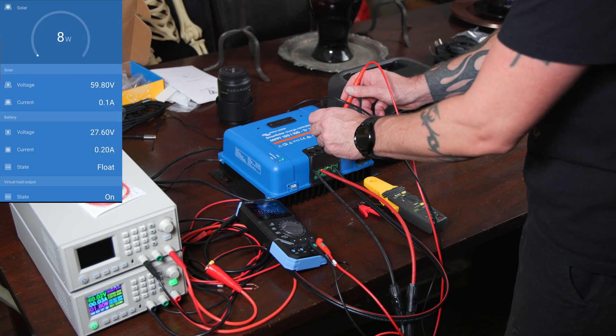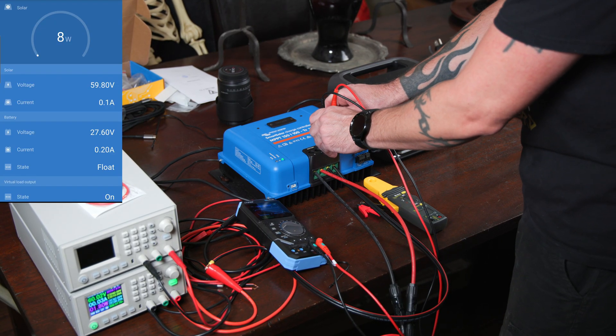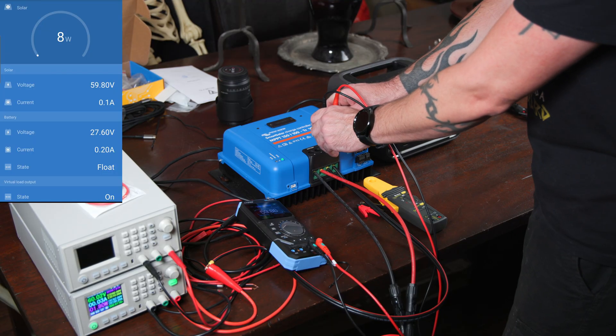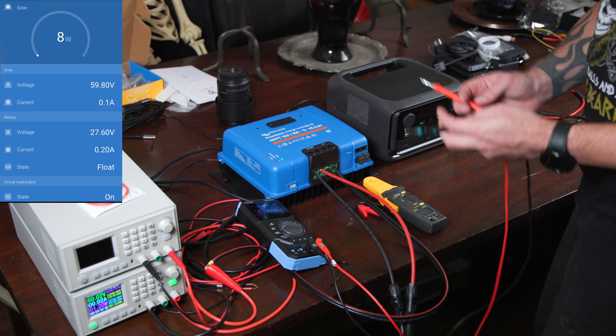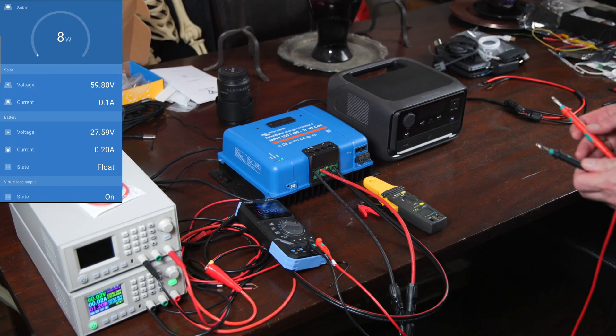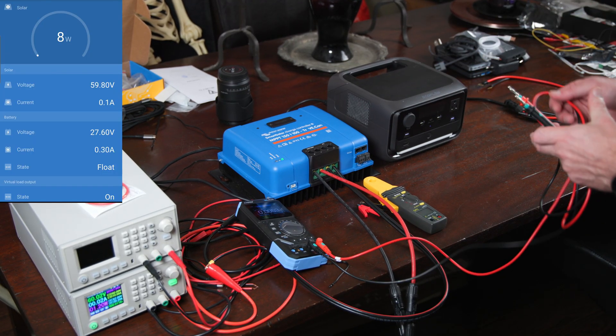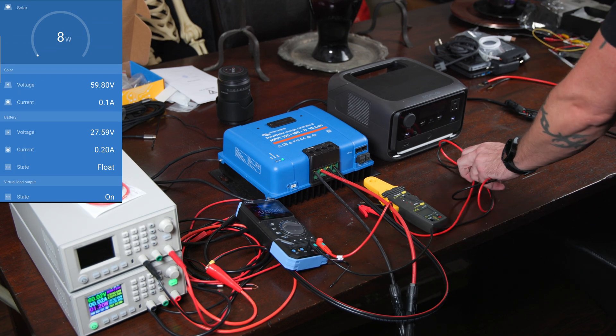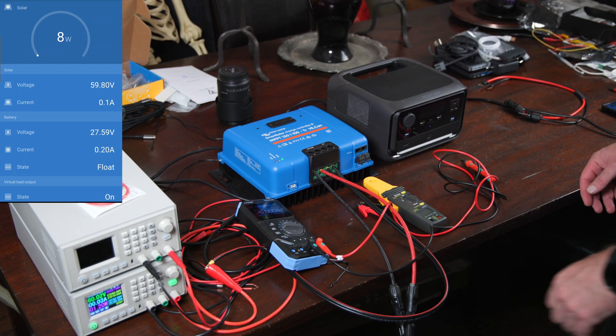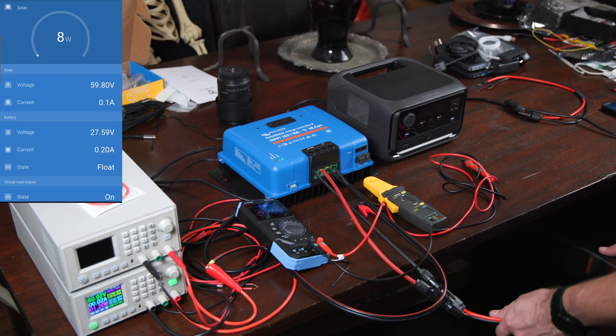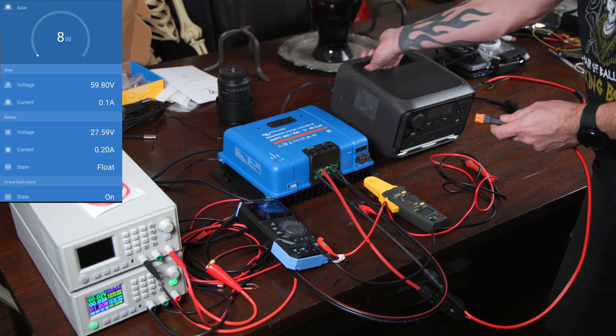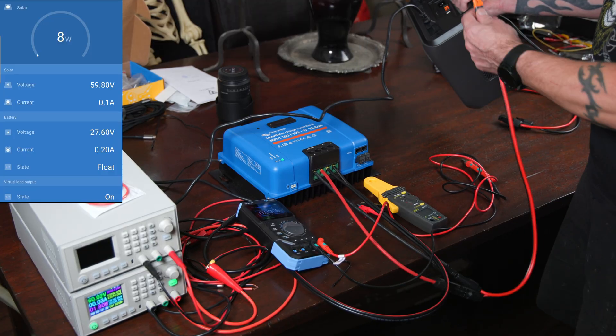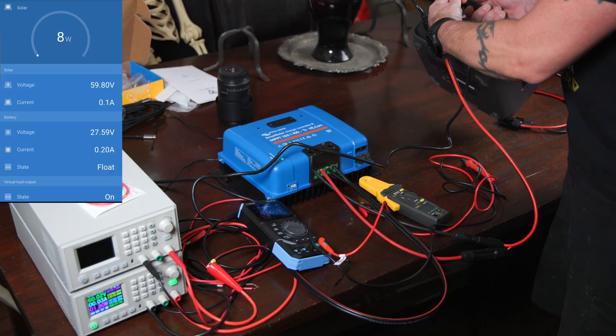So the battery side, which is what we're sending out, if we go and measure that, we have 27.5 volts. But the photovoltaic input, which is the solar side coming from the power supply, you can see we're getting 60 volts. The amps we can't measure until we get the load, so let's go ahead and connect it. Now we know the polarity is correct and we know that the voltage is not going to do any damage because we're within the specs.